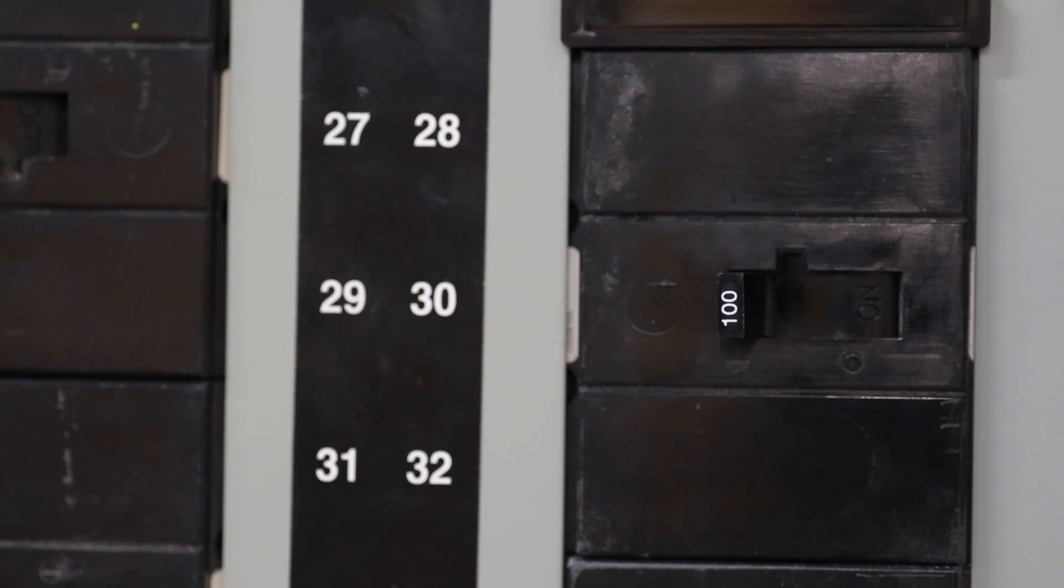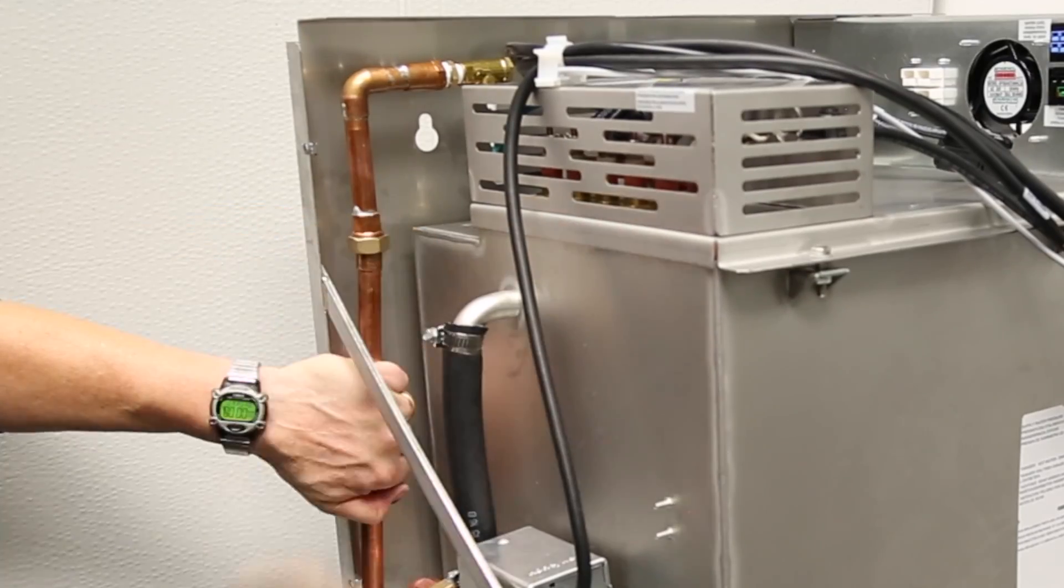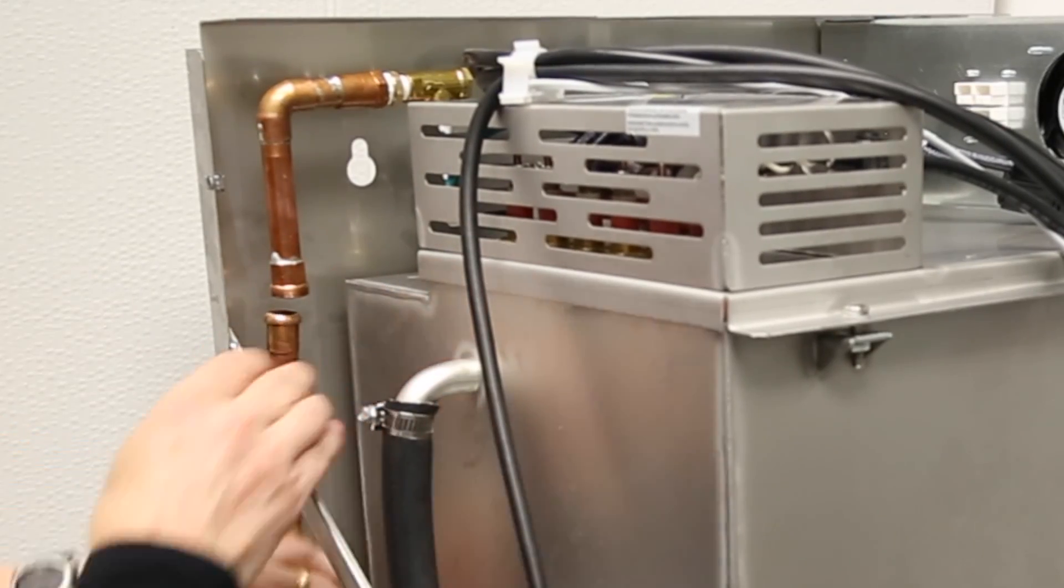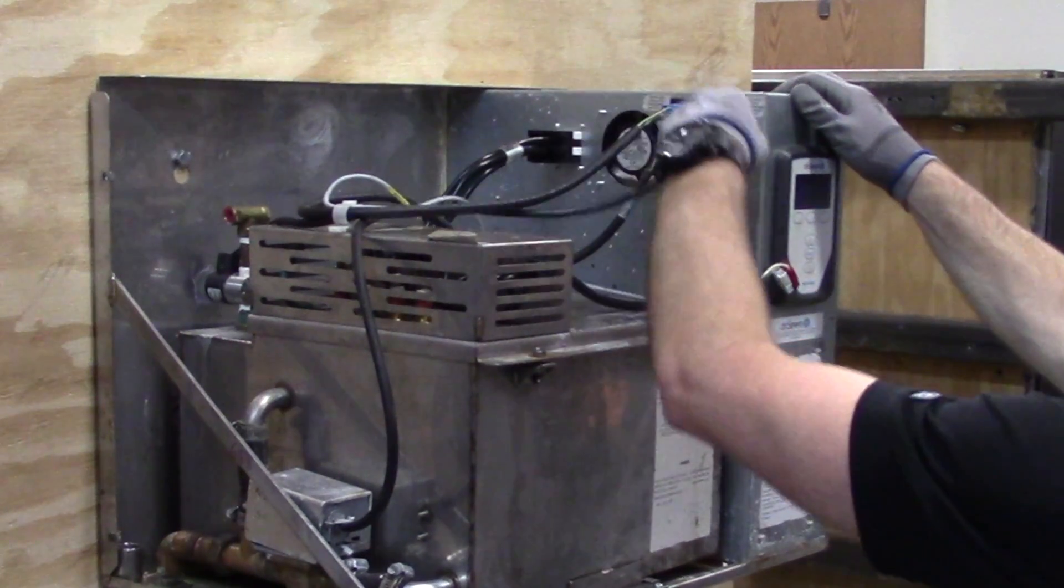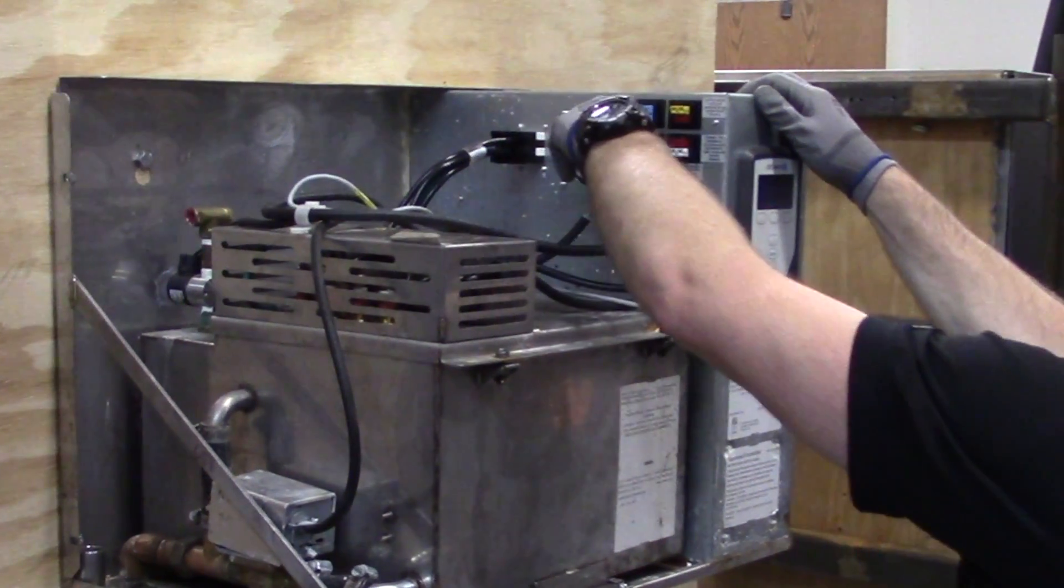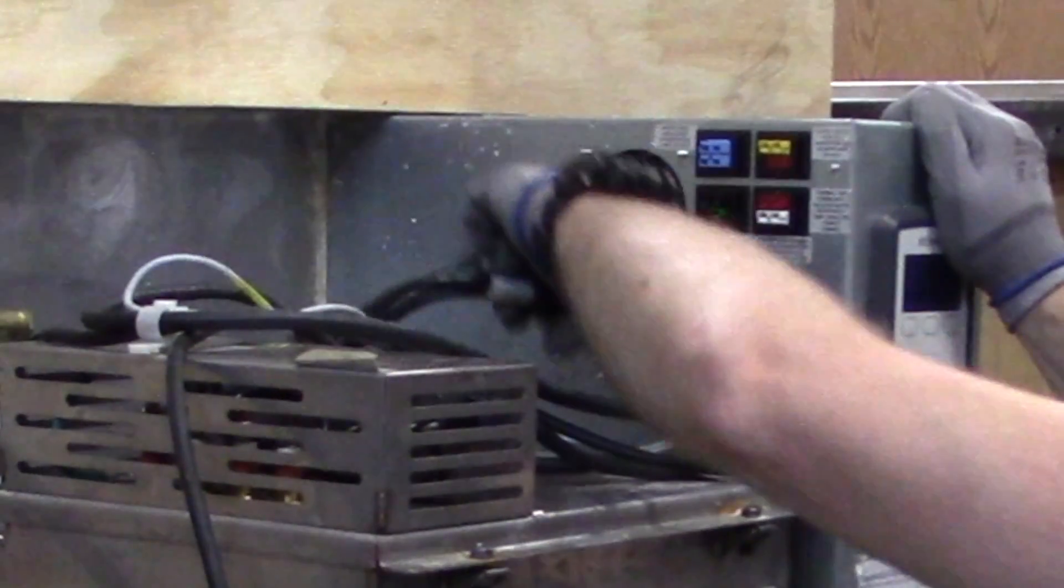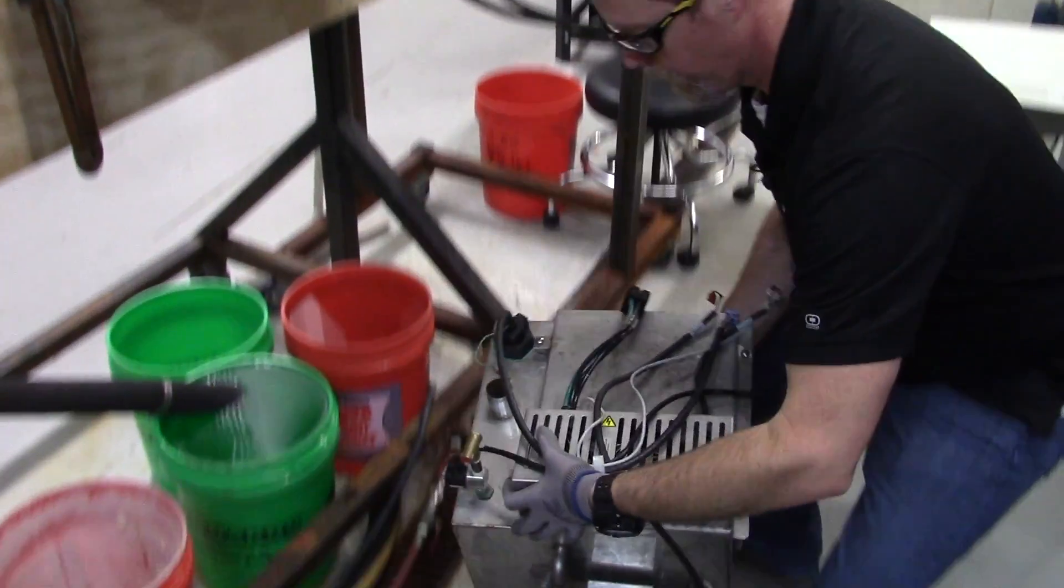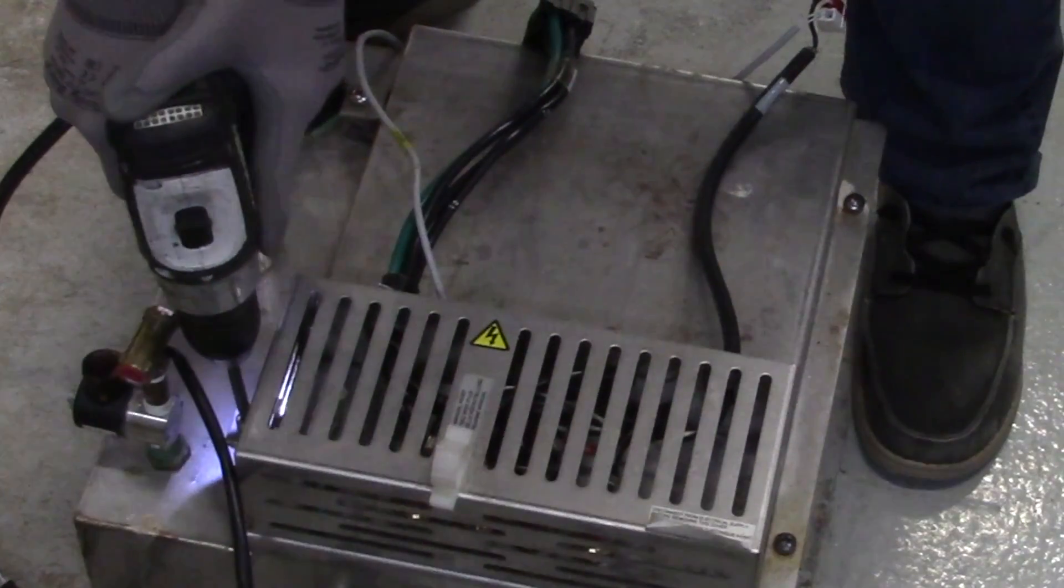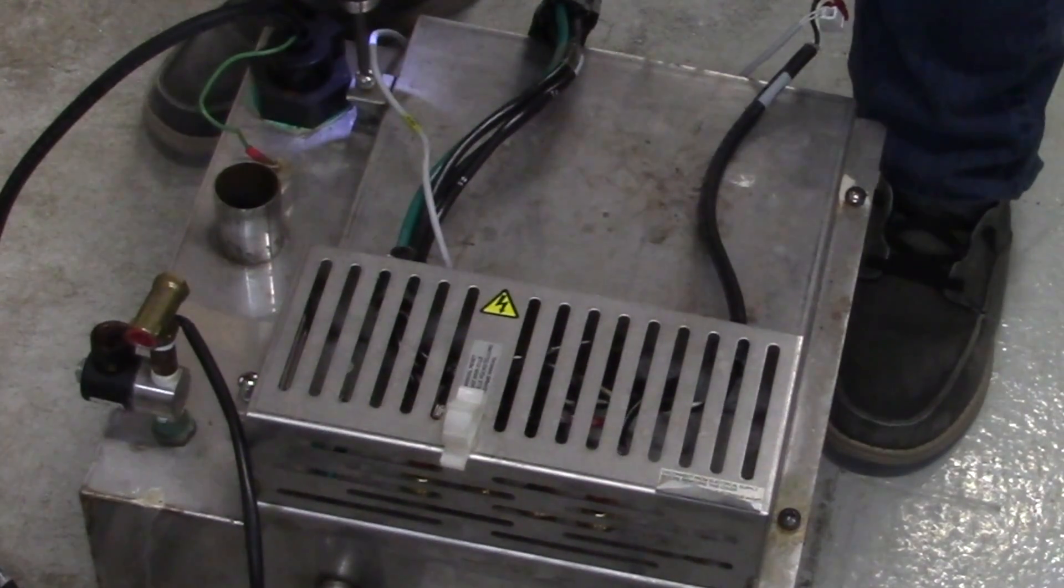Shut off the electrical supply. Disconnect the fill line at the supply side of the fill valve. Disconnect the electrical plugs between the tank components in the back of the electrical panel. Remove the evaporating chamber. Loosen the four cover bolts and remove the cover assembly from the tank.